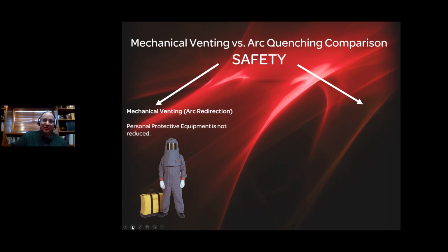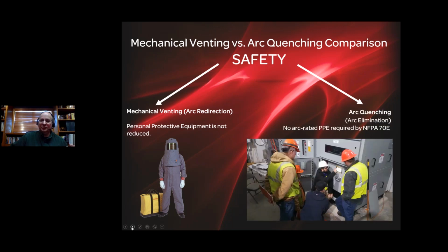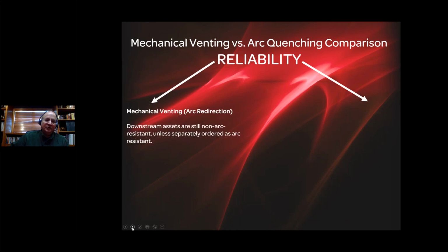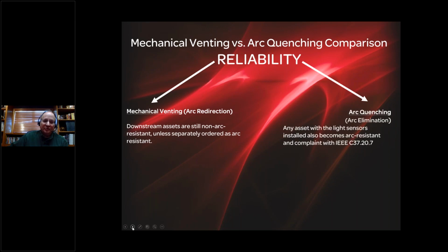In terms of safety, again, from a personnel point of view, with arc resistant equipment the PPE level is what it is. So the requirement for PPE is not reduced. Whereas you see here, you can tell the screen is energized, this was exposed energized equipment, but no arc rated PPE required by NFPA 70E, of course, whenever the arc quenching system is applied. In terms of reliability, downstream assets with mechanical venting are still non-arc resistant.